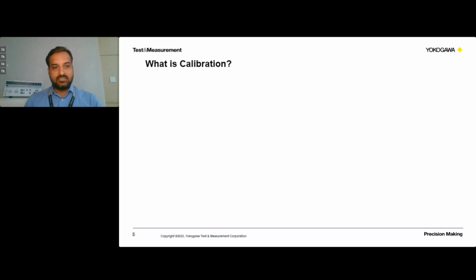So what is calibration? Basically, calibration is to compare. These days, when it comes to human beings, there is a trend of saying don't compare yourself with anybody, everybody is individual. But when it comes to test and measurement instruments, it is not so. Any test and measurement instrument needs to be compared with the known standard or the master instrument, which is of higher accuracy. The process of comparison is called calibration.